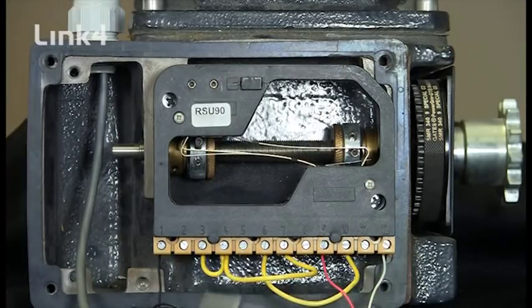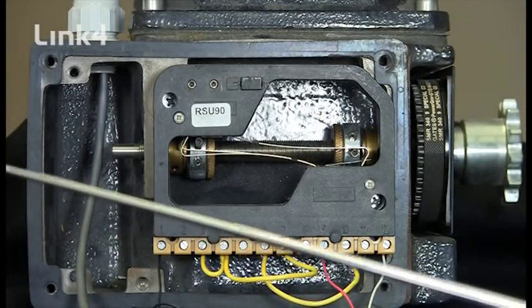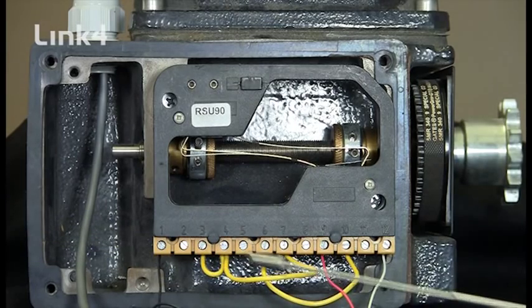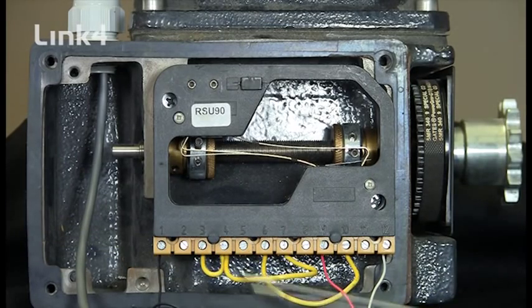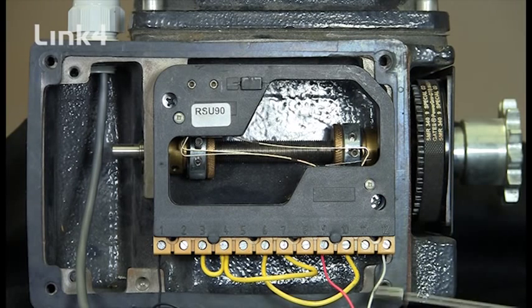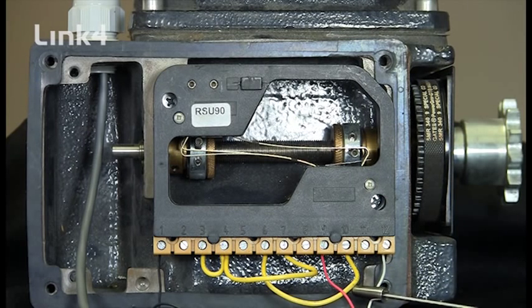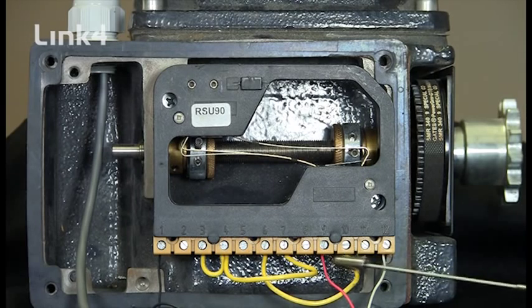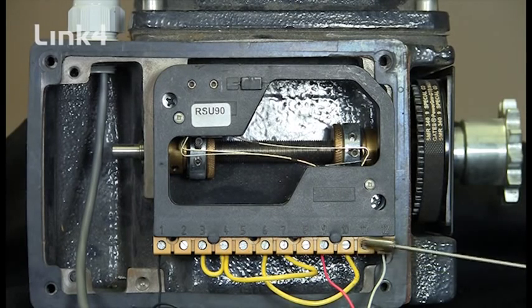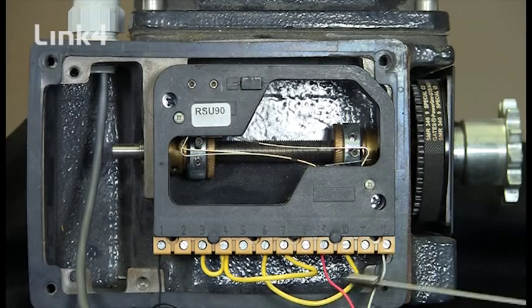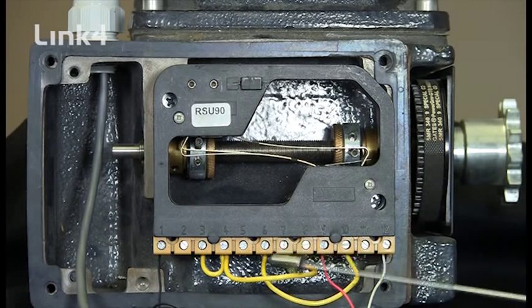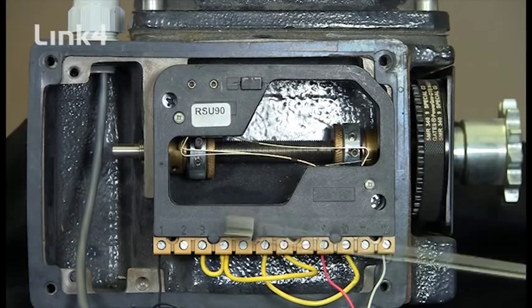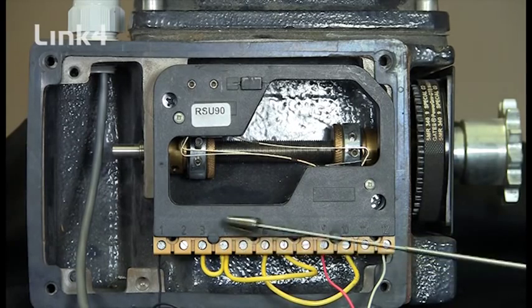Now we're going to connect the low voltage limit wire from the iDrive 300 over to the RW45. Our white wire comes in, that's applying 24 volts to the limit assembly. It comes in on number 12. It goes through the first secondary limit. It comes out on number 10 and jumpers over to number 6. Where it goes through the second secondary limit and comes out on number 4.